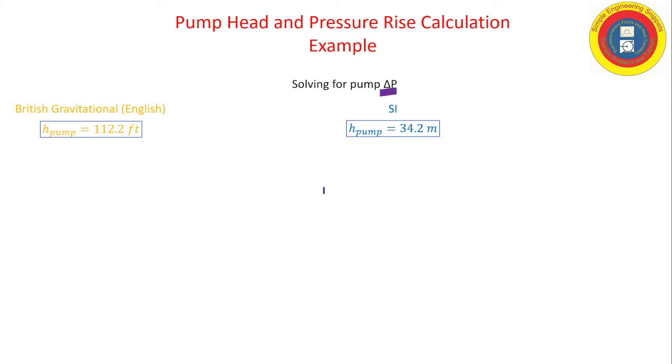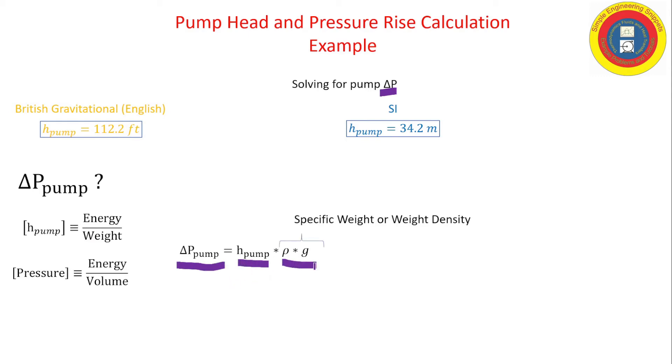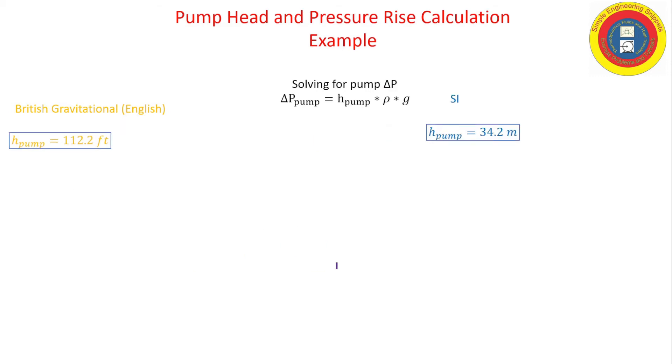Now let's work on finding the pressure rise across the pump. And again, let's look at the definition or the dimensions of our terms. Head is energy per weight, pressure is energy per volume. So to obtain pressure rise, I just take the pump head and multiply it by the weight density, also sometimes called the specific weight. All right, so let's do that for both systems of units.